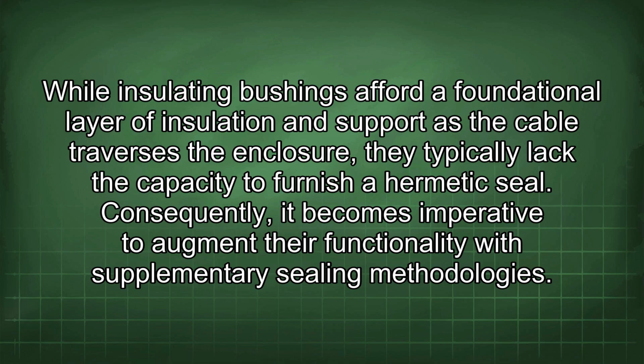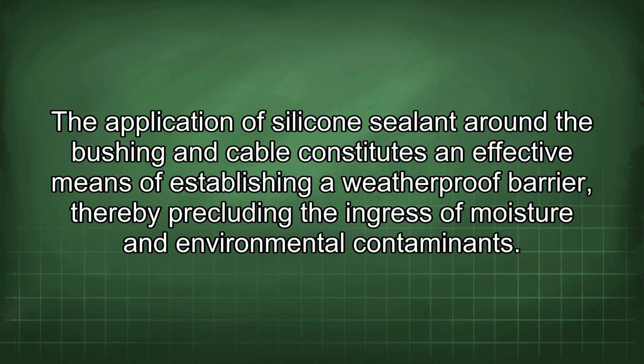While insulating bushings afford a foundational layer of insulation and support as the cable traverses the enclosure, they typically lack the capacity to furnish a hermetic seal. Consequently, it becomes imperative to augment their functionality with supplementary sealing methodologies. The application of silicone sealant around the bushing and cable constitutes an effective means of establishing a weatherproof barrier, thereby precluding the ingress of moisture and environmental contaminants.